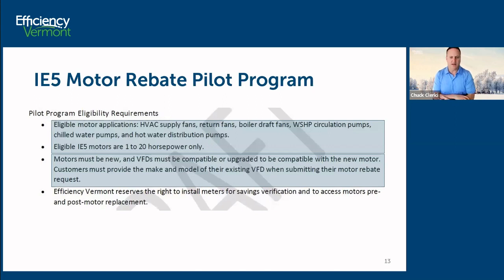Couple key points here. Back when I was talking about the VFD contractor incentive program, we were talking about 7 end-use applications. The motor applications in this program are the same 7 minus the cooling tower fans. And the reason for that is the IE5 motors that we have available today are not waterproof, and we don't want to risk putting these in damp locations and having motor failures or worse.